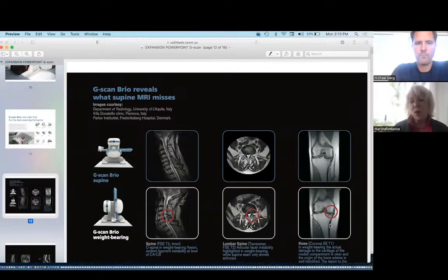We're smaller. We don't radiate that much heat, so we don't need to have a cooling system. The other MRIs are running between $3,000 and $4,000 a month in helium cost. So right there, that's a $6,000 minimum savings just on running costs with us. An average lease is about $13,000, which is really easy to break even. If they're doing personal injury, they get reimbursed between $600 and $3,000 on average per personal injury MRI.